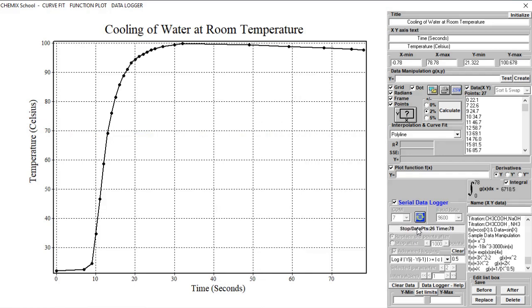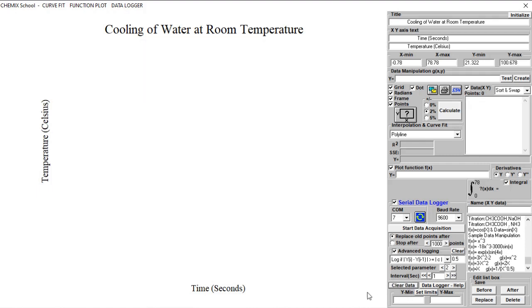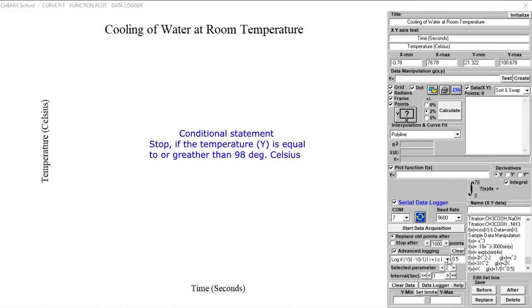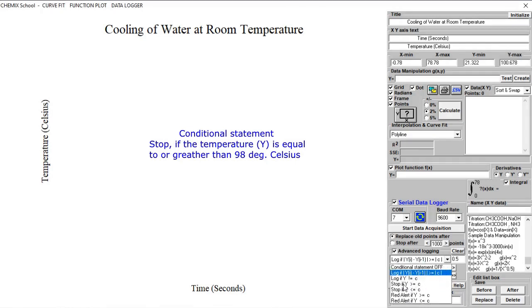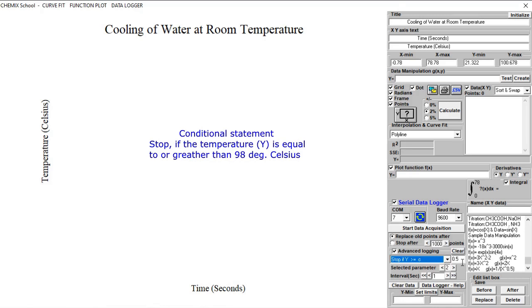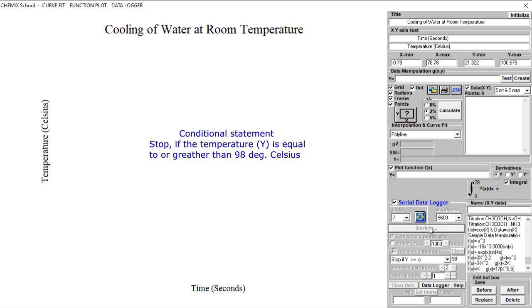Click the Data Acquisition button again to stop logging. Remove the data from the XY Data field by clicking the Clear Data button. To stop logging when a certain temperature condition is fulfilled, select a stop condition from the drop-down menu and insert the temperature in the right text field located below the Clear button. As we can see in this example, when the sensor reaches a temperature of 98 degrees Celsius or more, the logging process will automatically be stopped.